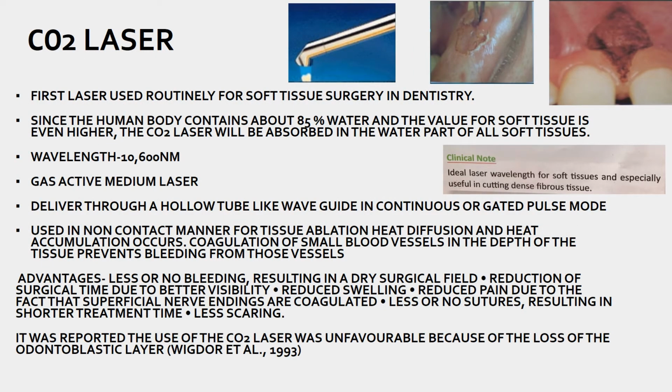Next is the CO2 laser. It was the first laser which was used routinely for soft tissue surgeries. Now since the human body contains about 85% water and the value for the soft tissue is even higher, this CO2 laser will be absorbed in the water part of all the soft tissue. Now the wavelength is too high, 10,600 nanometers. Then the active medium is a gas active medium.